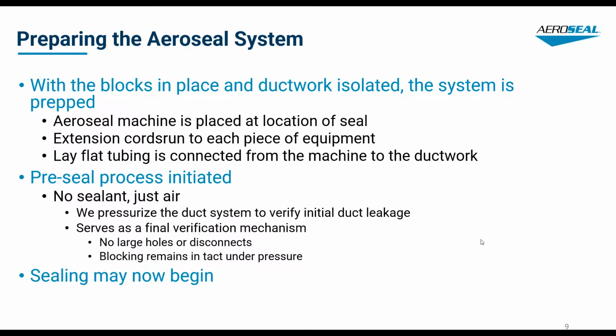With the blocks in place and ductwork isolated, the system is prepped. The Aeroseal machine is placed at the location of seal. Extension cords run to each piece of equipment, and lay flat tubing is connected from the machine to the ductwork.